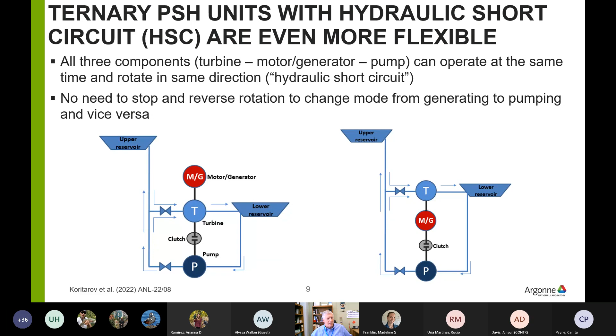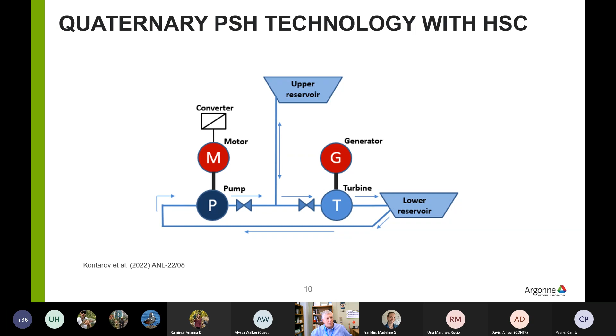These configurations provide even more flexibility because if the turbine and pump apply hydraulic short circuit, they can operate at the same time, and you can easily regulate the power output either in generating mode or in pumping mode. So these ternary units can operate from plus 100% of capacity all the way down to minus 100% in the pumping mode. And finally, the quaternary technology has even the motor and generator separated, so we have four components here, and that's why it's called quaternary. It can also operate in hydraulic short circuit, so pump and turbine can operate at the same time and provide great flexibility, basically from minus 100% to plus 100% of capacity.